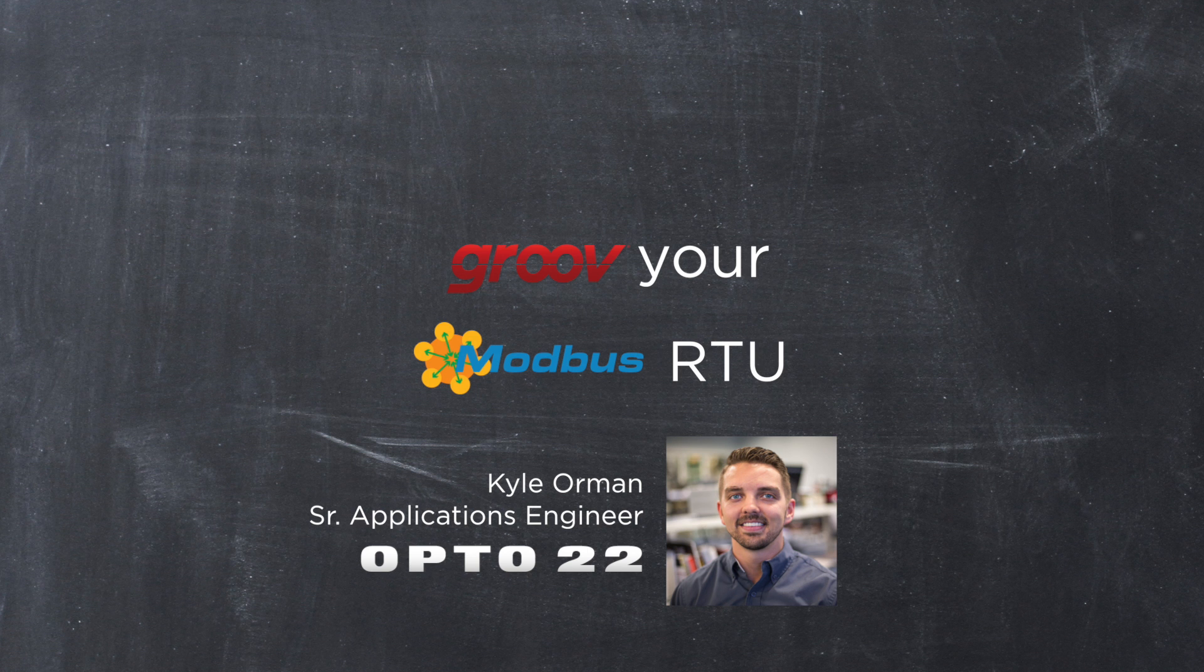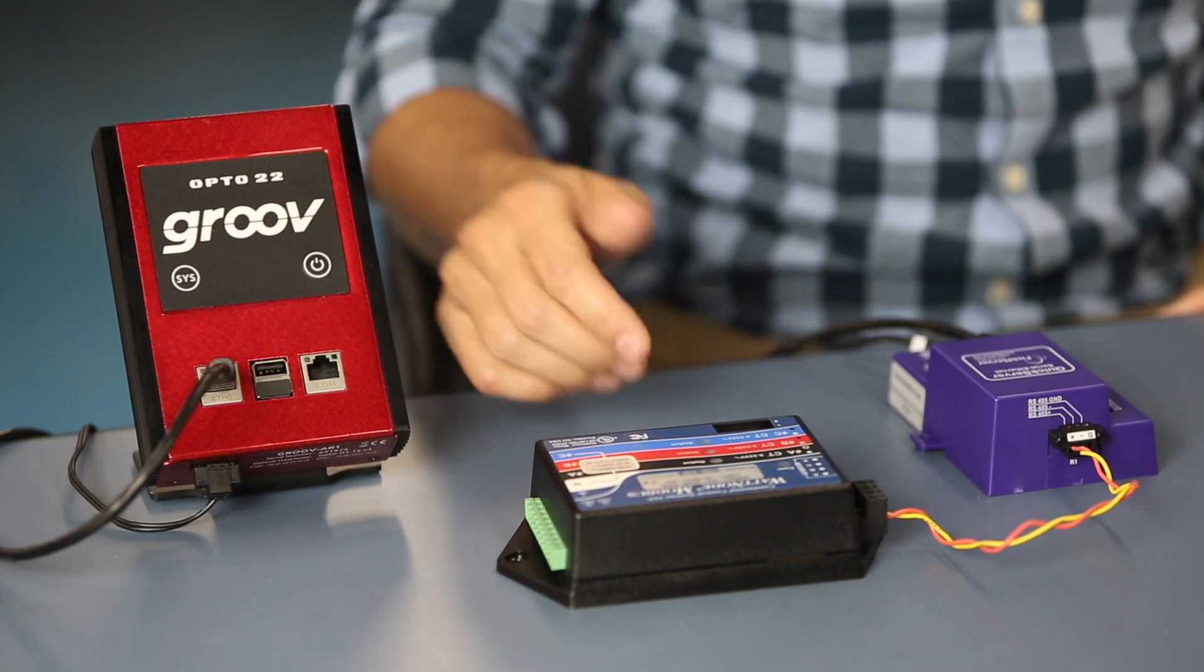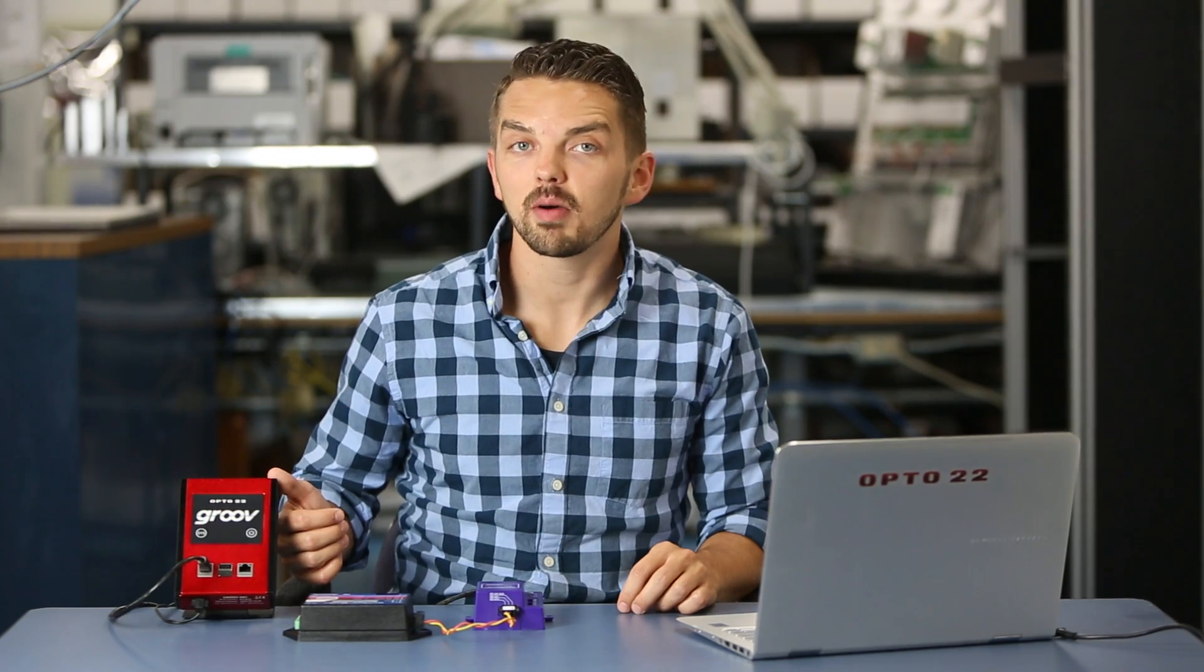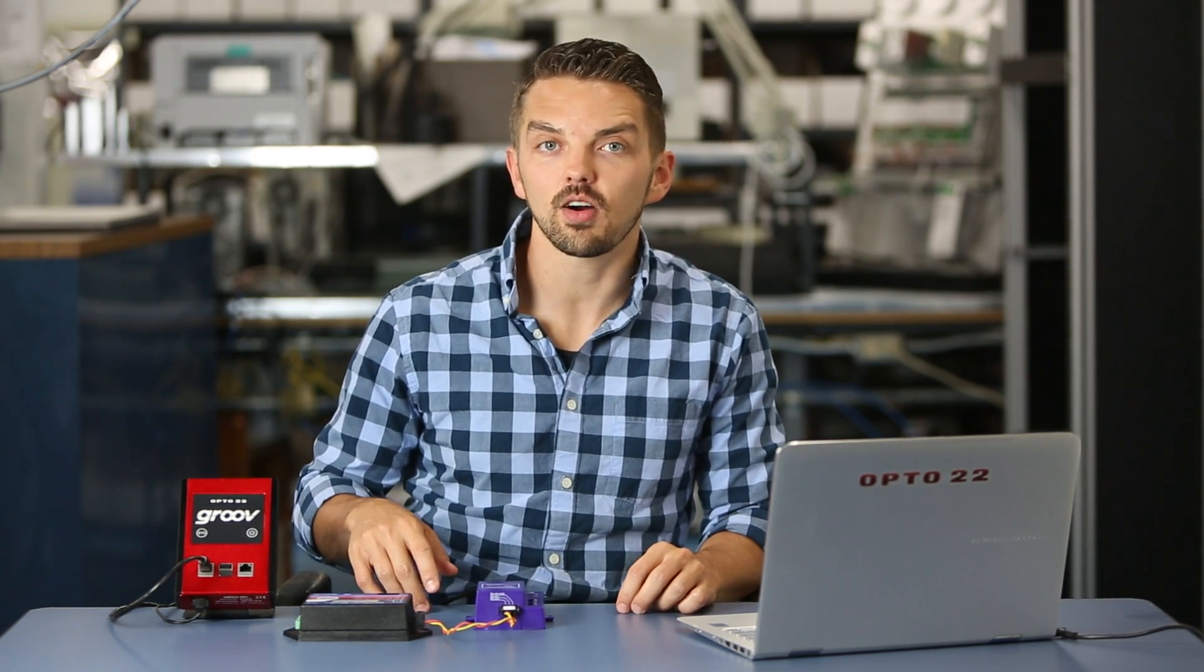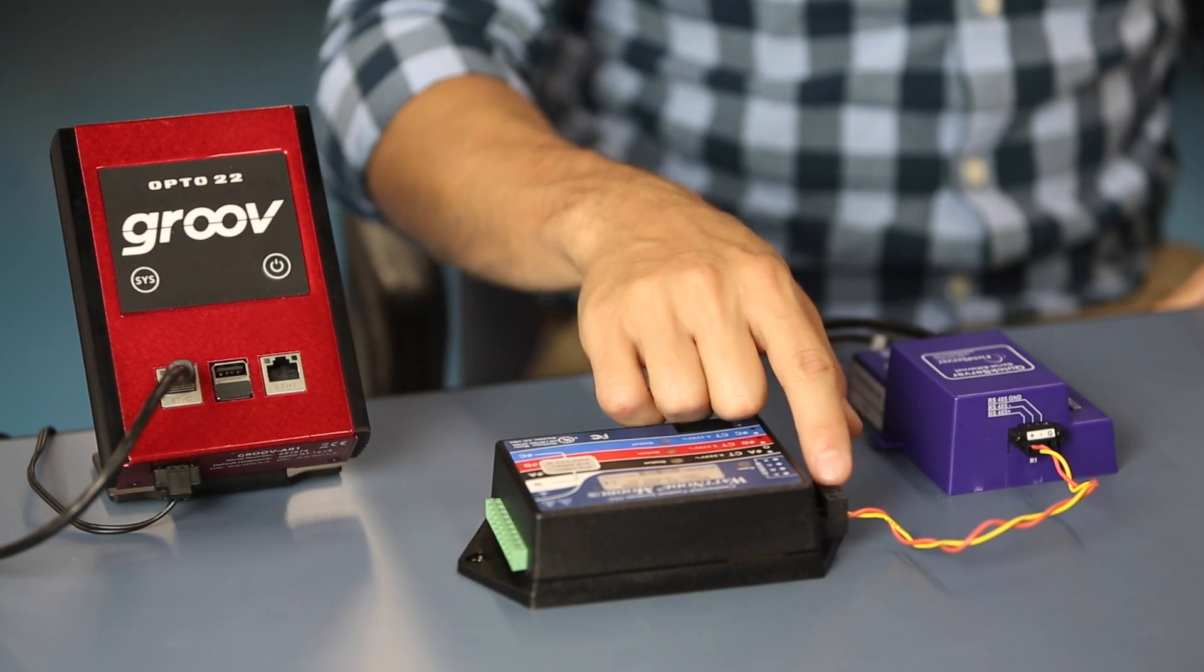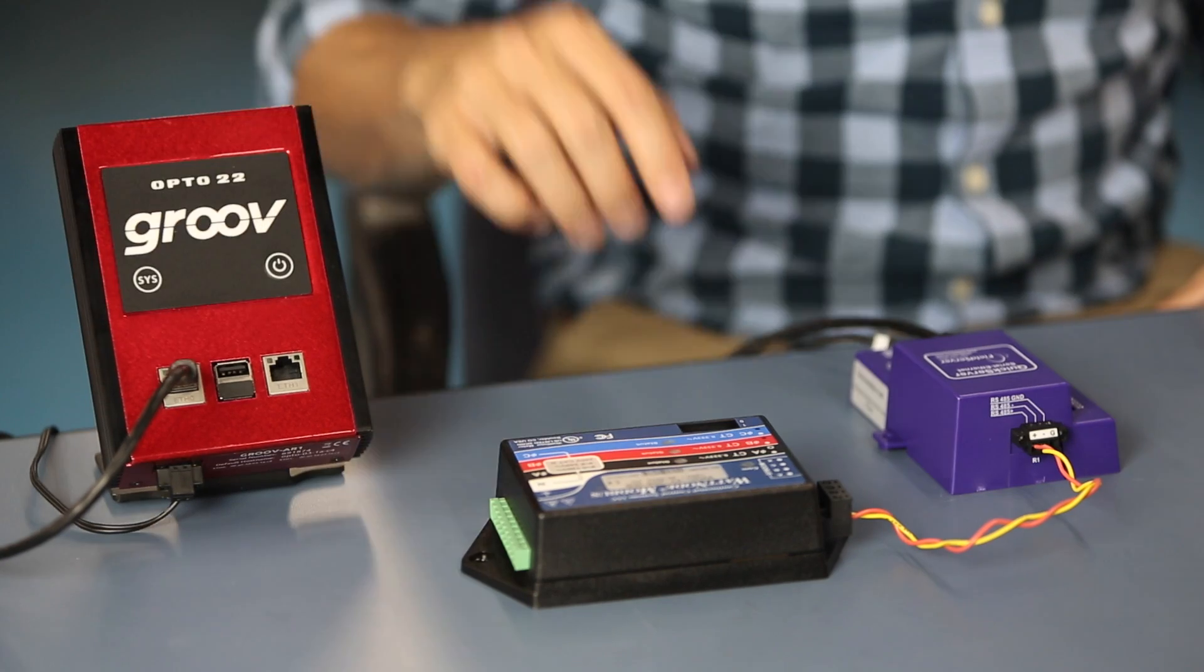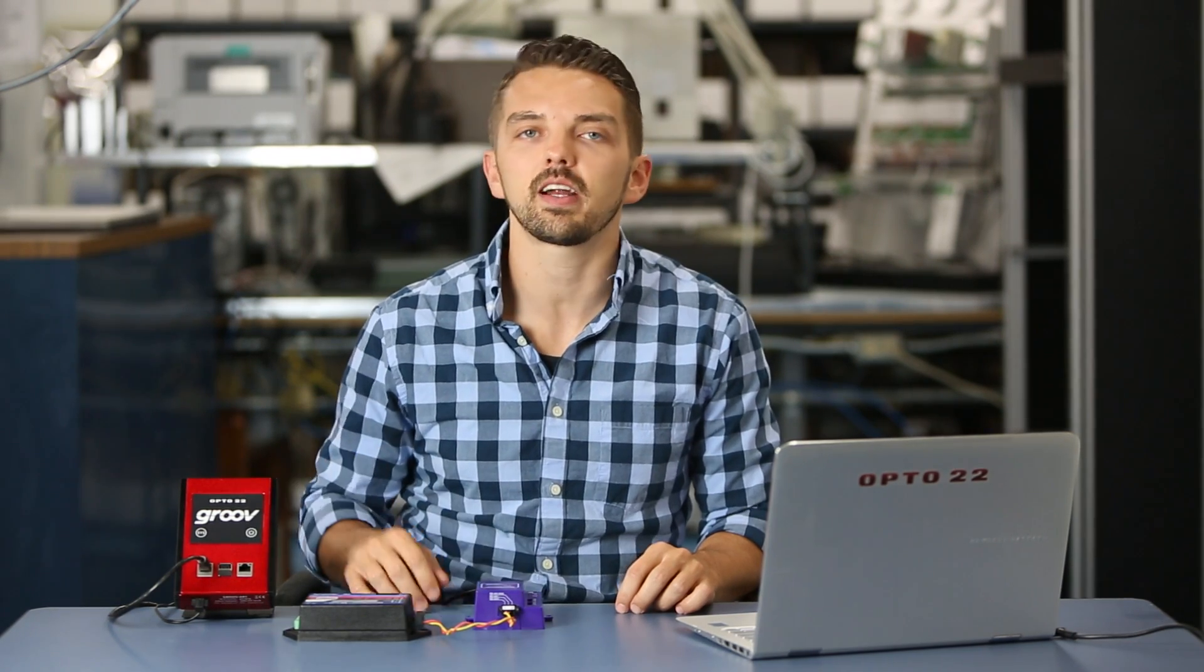Hello, I'm Kyle Orman, Senior Application Engineer here at Opto22. Today I'm going to show you the critical steps you'll need to know to connect your Modbus RTU device into groov. From a high level, we're simply going to take an RS-485 signal and put it onto a Modbus TCP network, which is especially useful because groov inherently speaks Modbus TCP.